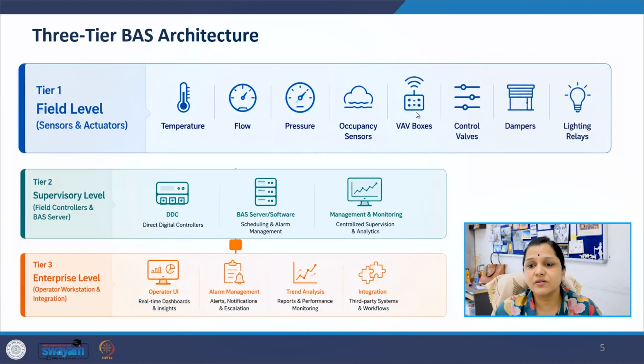So, building automation system has a three-tier architecture. The building automation systems are commonly organized into three-tier architecture. The first tier is the field level. This includes sensors and actuators installed throughout the building. Temperature sensors, occupancy sensors, VAV boxes, dampers, and lighting relays all operate at this level.